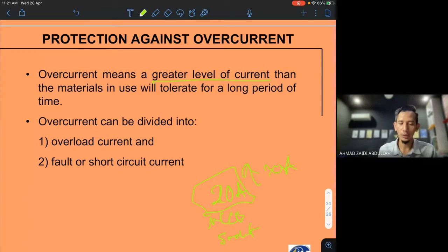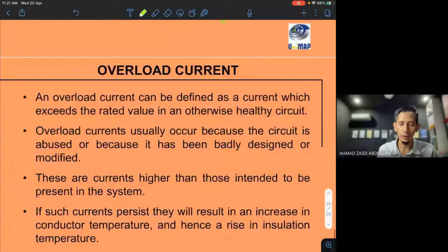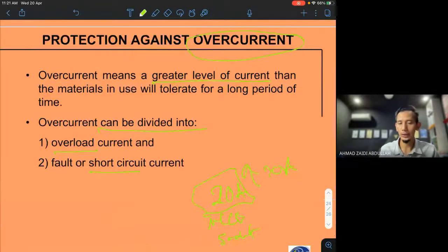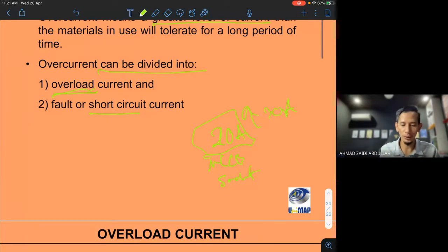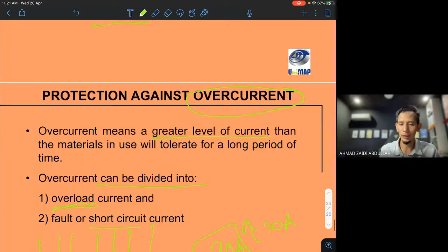So overcurrent can be divided into two. First is overload current, and number two is fault or short circuit current. Normally we just say overcurrent, but under overcurrent we have two. So if you check back your design, your schematic diagram that you drew last week, this one is the ELCB, and below that you have the MCCB. This we call overcurrent protection.